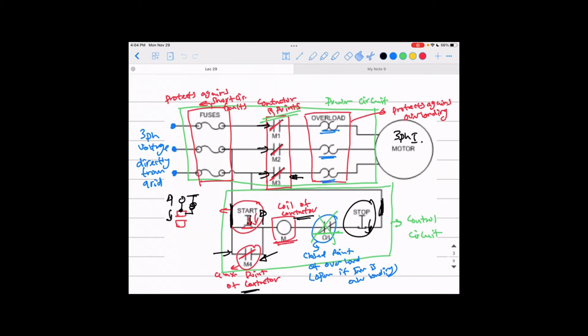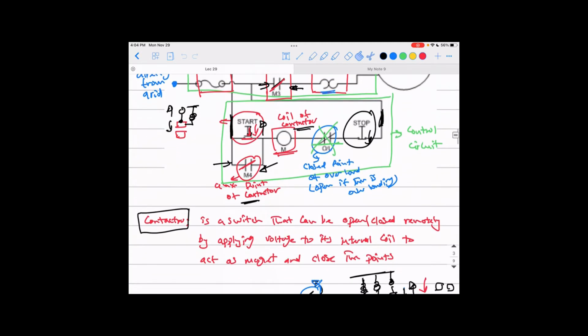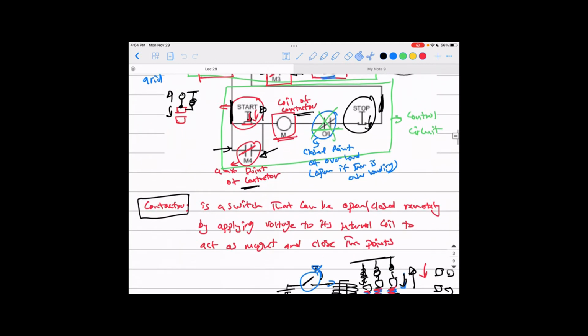Okay, and you have two pieces of protection. One of them is a fuse. It's a protection against short circuits, and an overload relay, which is protection against overloading, which is a small increase in the current but lasts for a long time, contrary to the fuse, which protects against short circuits, which is a very high current that just lasts for a small period. Okay, and that was the control circuit, which has basically two push buttons, one for the start and one for the stop.